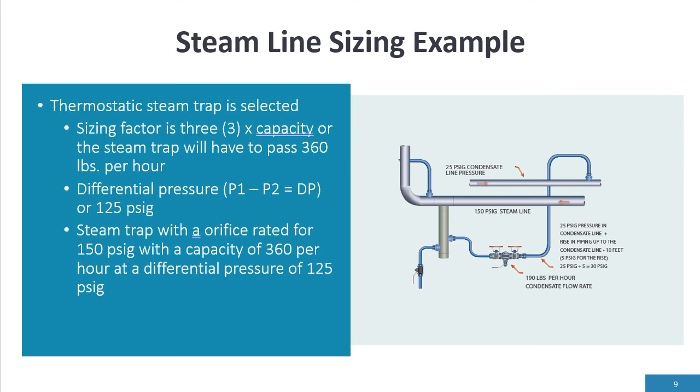I go and the sizing factor is three. I'm going to use the thermostatic design steam trap. So three times my capacity, I have to pass 360 pounds per hour condensate. My differential pressure is 125 psi.